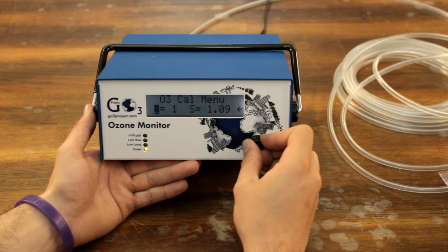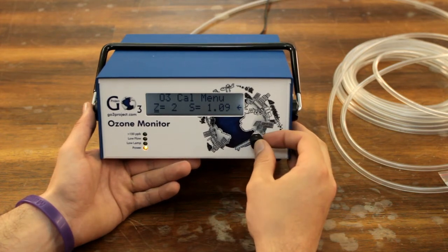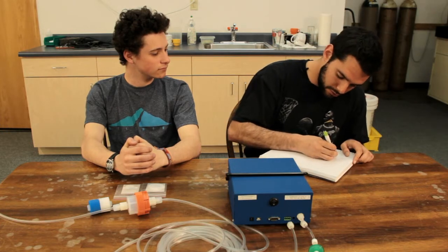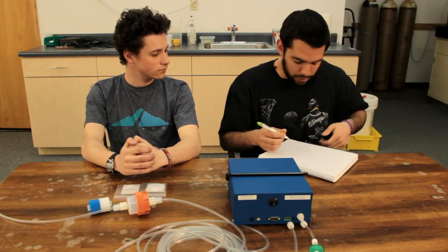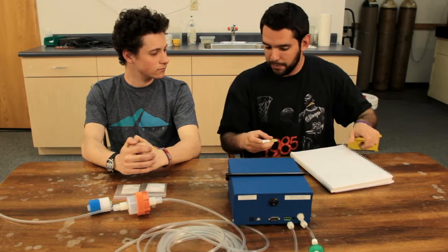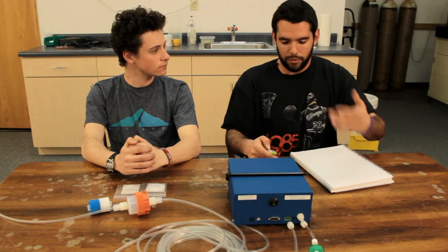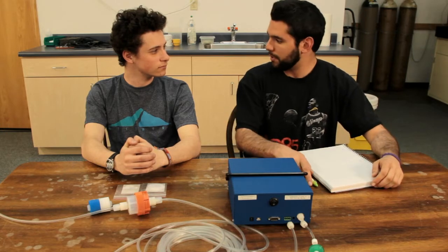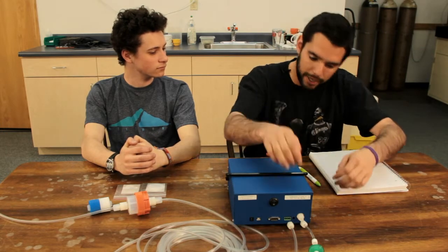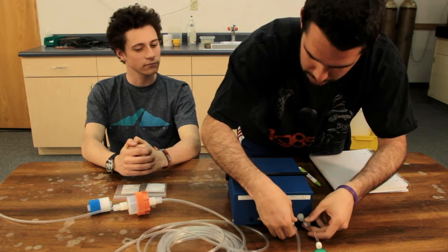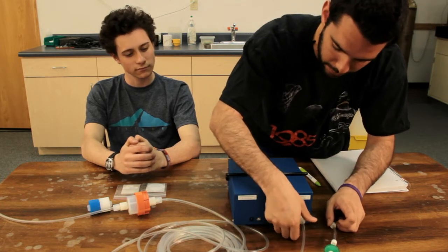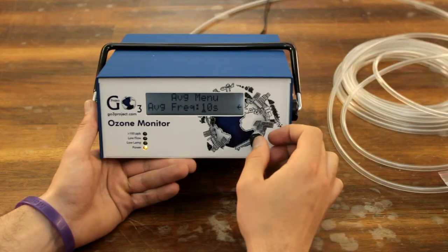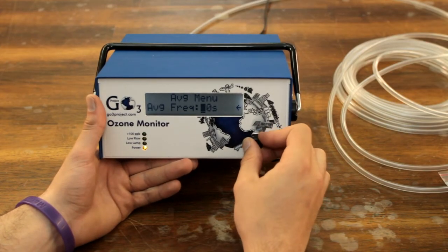Once we've done that, we'll go back into the same display screen again and take another 20 measurements to see what kind of average we get. If it's anywhere in between -1 and 1, we've accounted for our offset and we've changed our Z, and everything should be correct. After you've done that, you can unattach the ozone scrubber and reattach your filter housing. You can go back in and change your upload time to 15 minutes again, and you can continue uploading.